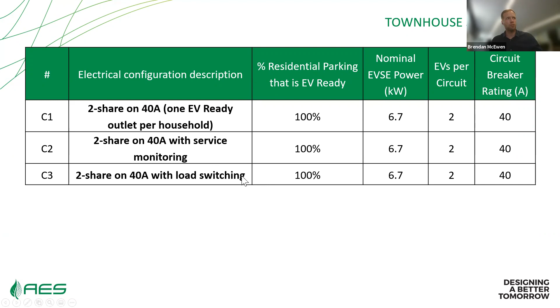With load switching, you've got equipment that says your dryer can be on or your EV charger, but not both. That allows you to avoid upgrading from a 100 amp panel to the next highest panel capacity, 225 amps.